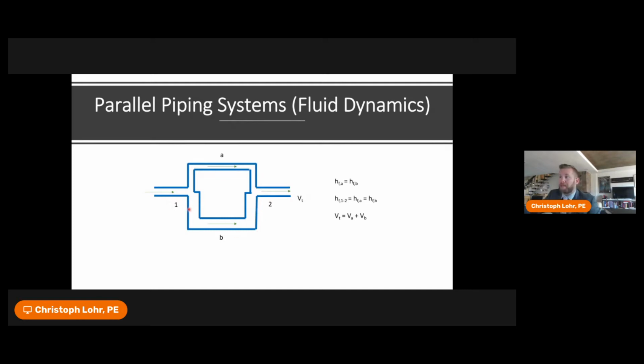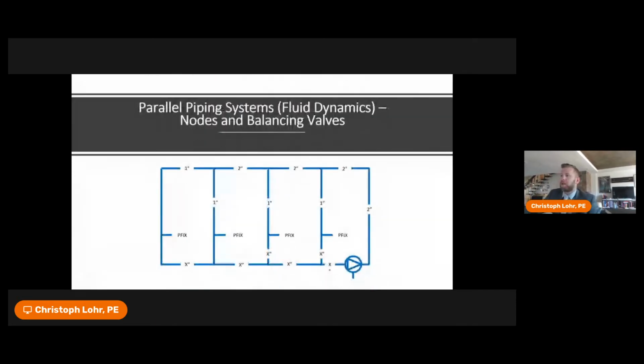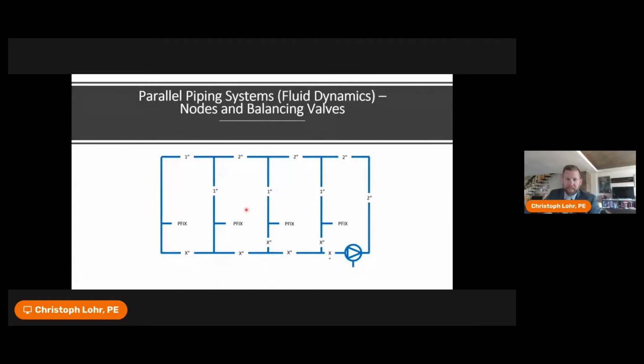You could do that by making B a longer loop. You could do that by reducing the size of B. And the most common methodology, and the quickest answer that most engineers who get this question right give, is you can add a balancing valve on B and restrict the flow. That creates an artificial pressure drop, if you will. So we take that same concept and writ large.